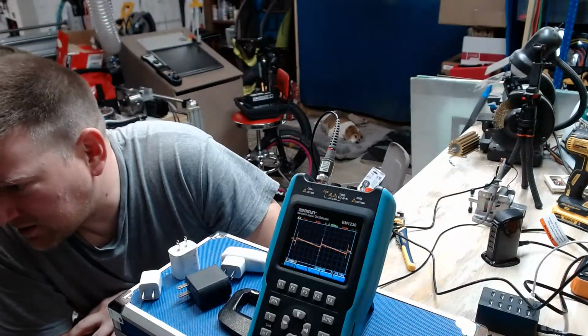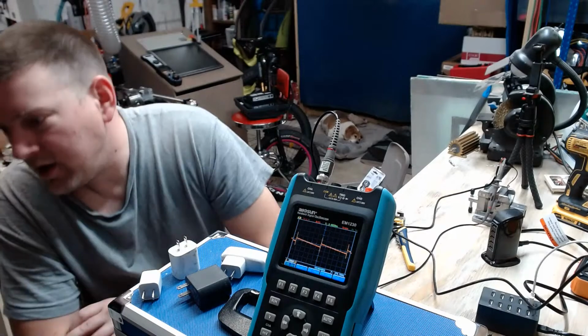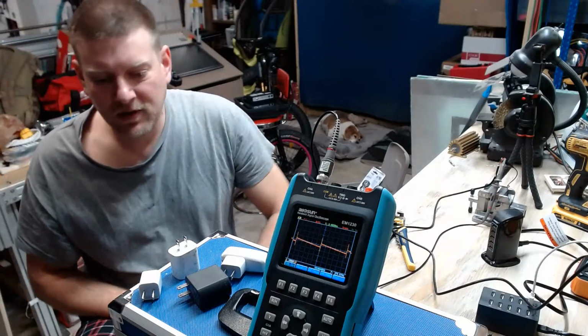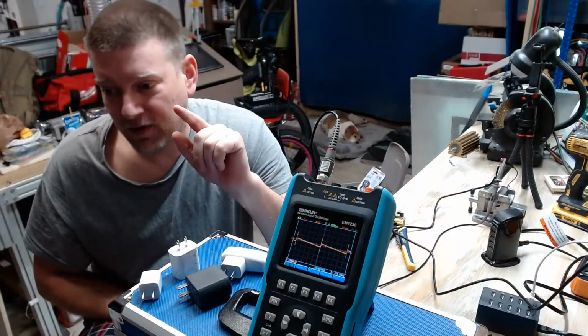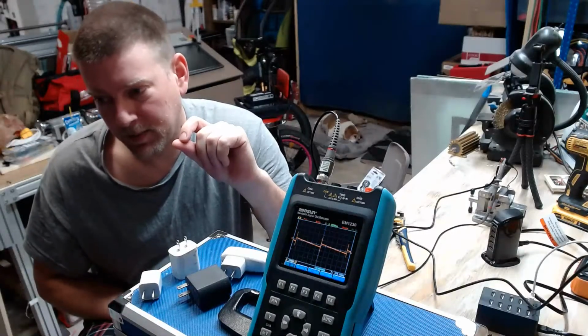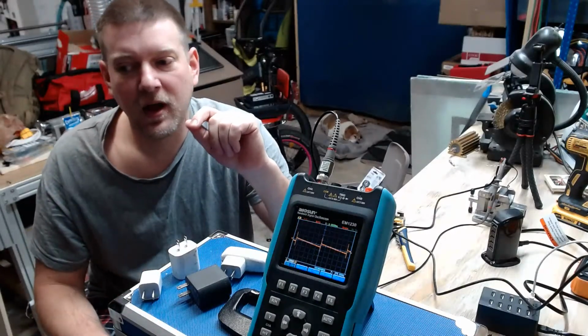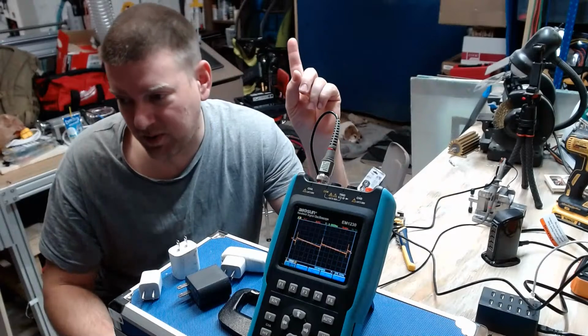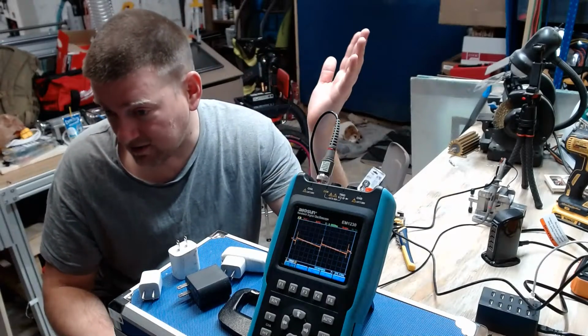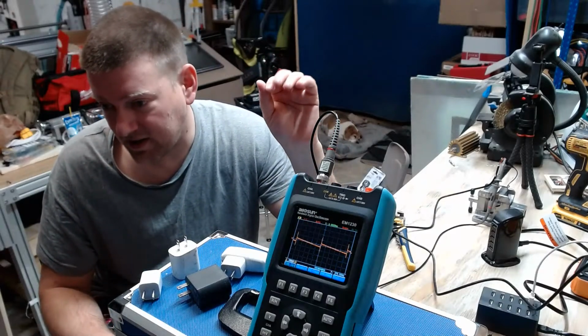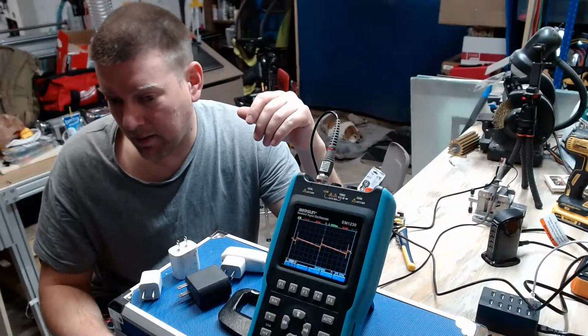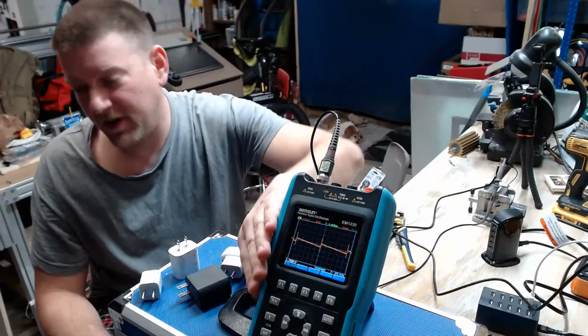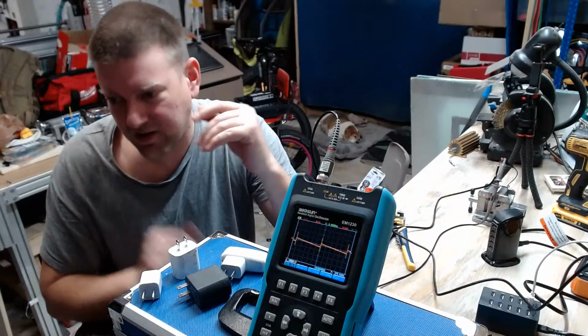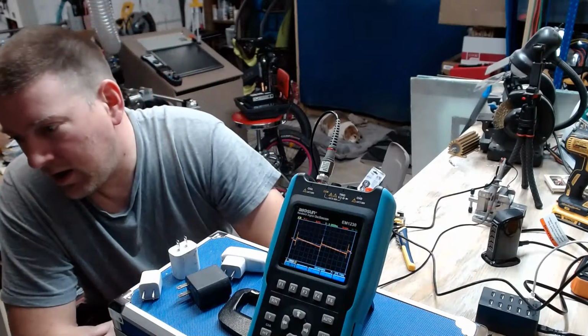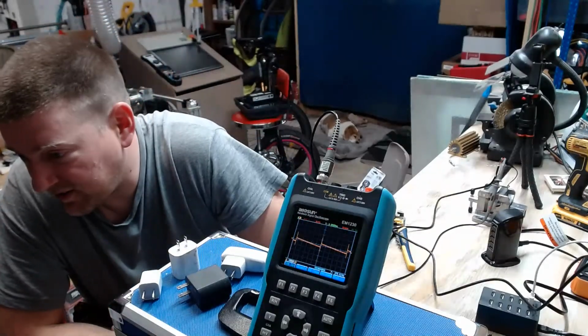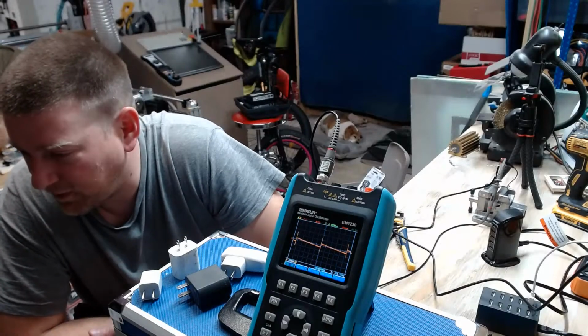How do EKG systems have filters and shielding? You know, EKG does have filters, but normally the filter is for 60 hertz - it's a 60 hertz notch filter. And the reason they do that is because your lights, specifically your fluorescent lights, they're going to be 60 hertz. Other devices that have AC in close proximity are going to be 60 hertz. So yeah, 60 hertz is going to be your basic filter.